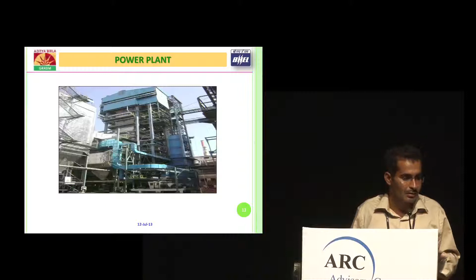These boilers are designed for 64 ATA and 485 degrees centigrade. Many of you sitting here will be surprised at the pressure levels in the plant. As I said earlier, this is a captive cogen plant, and steam is required much more than power. So we cannot afford to go for higher pressures because we need to extract more steam out of the turbines.